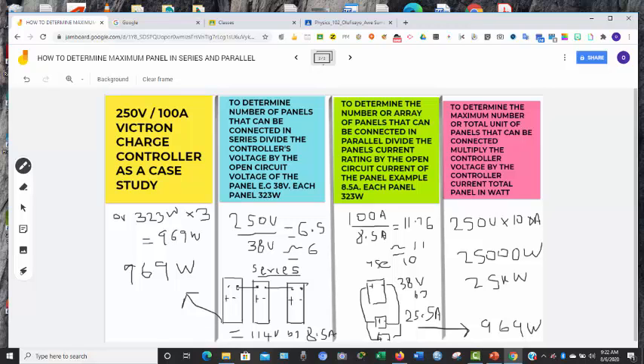I have three panels, and the wattage for each of the panels is 323 watts times 3. In the case of series, it will give me 969, and similarly with this one. If you want to check further, 114 volts times 8.5 amps will still give me 969 watts. Then 38 volts multiplied by 25.5 amps will still give me 969 watts. And if I take the wattage of the panel directly and multiply it, 323 watts times 3 will still give me 969 watts. So with this, I know that if I'm using 3 panels on this charge controller, it is far, far, far lesser than what the charge controller can take.